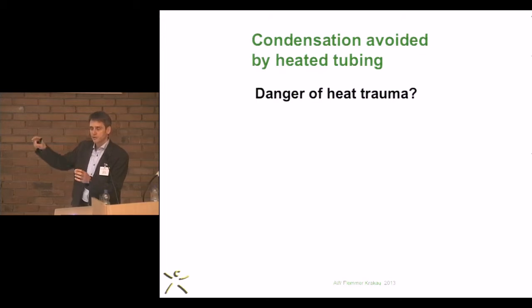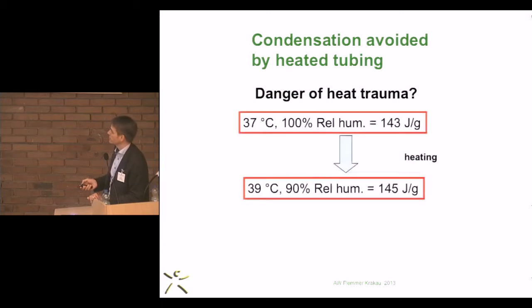And subsequently, the inspiratory limb of the tubing is heated up to 40 degrees. Is that a problem if a higher temperature reaches the trachea? Actually, you can calculate that, because 37 degrees, 100% relative humidity bears an energy of 143 joules per gram.